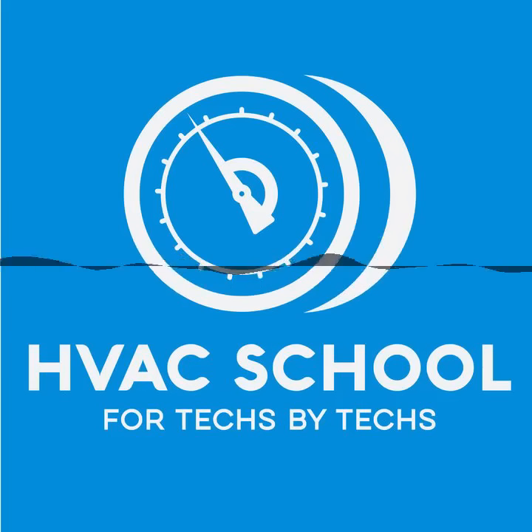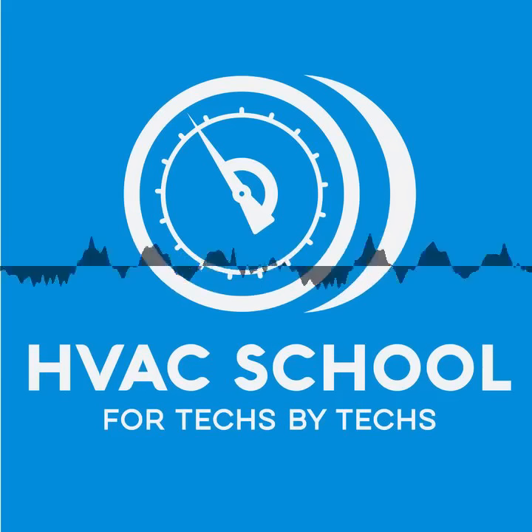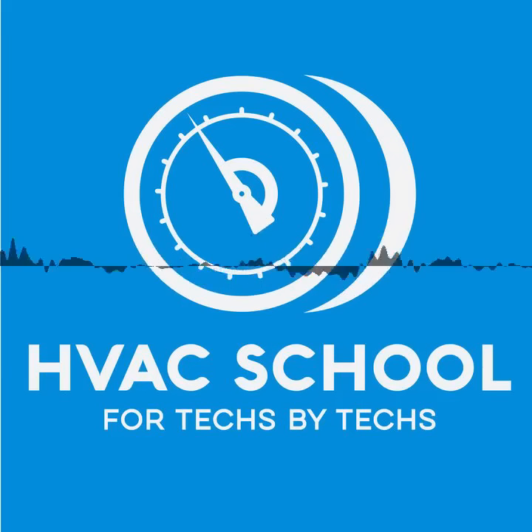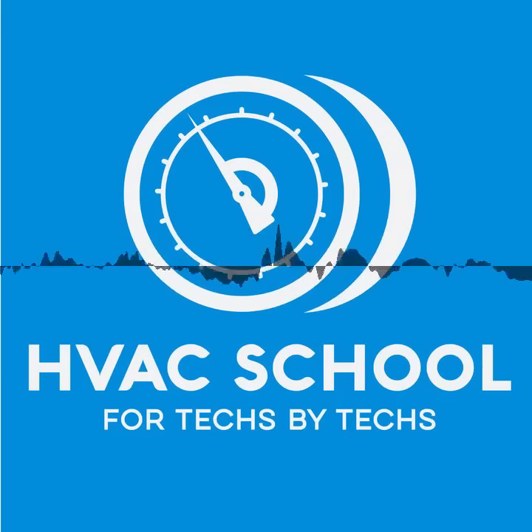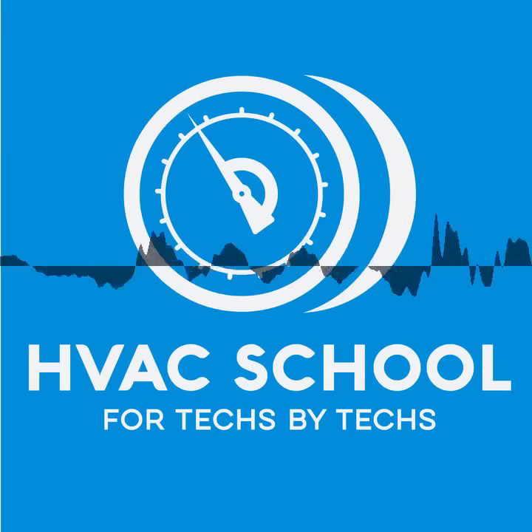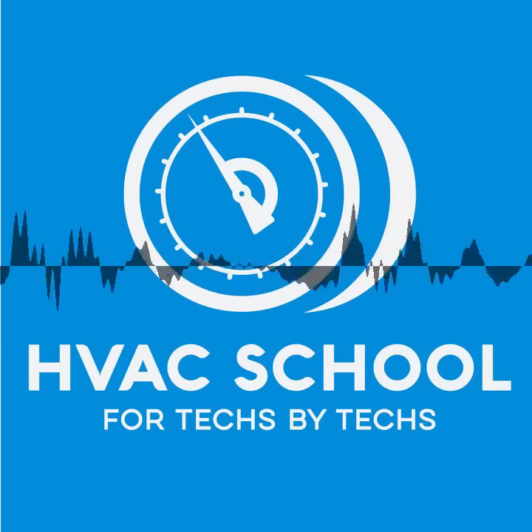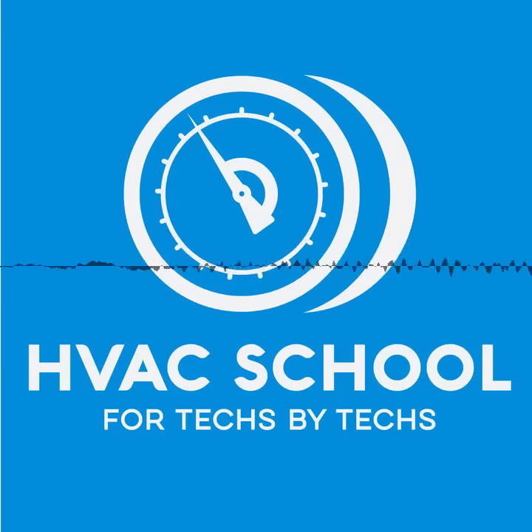It might be a good idea whenever you're working on a big water system like this. You definitely want to coordinate with building maintenance, have their phone numbers available in case there's an emergency. And maybe if you have enough experience, have them show you where the pumps are and the makeup water is. And if the worst happened, you have to shut off the pumps and the makeup water. Somebody's going to have to. It doesn't matter at that point. You have to shut it down. Water is going to flow, and hopefully you're not on the ground floor and have 17 stories of water above you, but hopefully you never have to be in the situation. But always be prepared in case it happens, not just stand there watching it like, oh well.